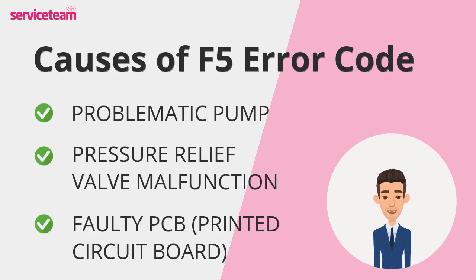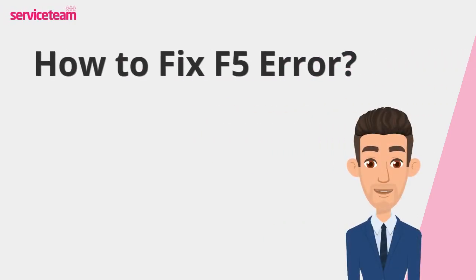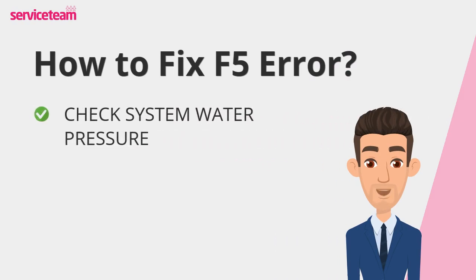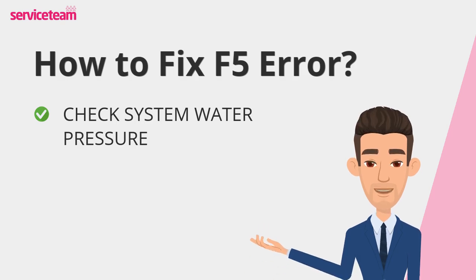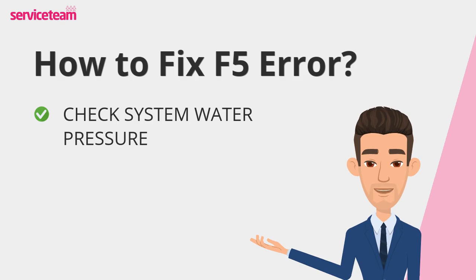Understanding these causes is the first step toward getting your boiler back on track. Let's find out how to fix the F5 error code. First, check your boiler's water pressure — it should read between 1 and 1.5 bar. If it's too low, use the filling loop to top it up. Refer to your manual for detailed guidance. Glowworm boilers need the right pressure to work properly, and low pressure is a common cause of the F5 fault.